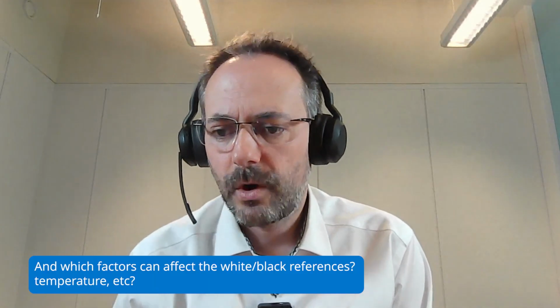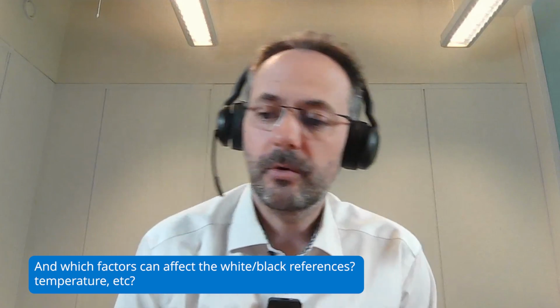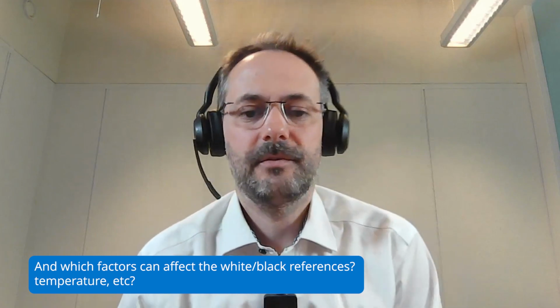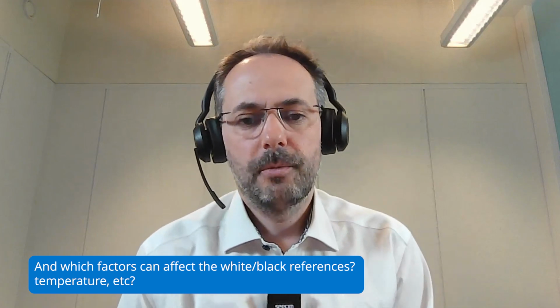Which factors can affect the white and black reference, temperature, etc.? Okay, I think I already gave a kind of answer, but I can repeat it. About the white reference, it sees mostly the illumination. So it is actually seeing the incoming light. So what can affect it? It is if you change any camera parameter, for example, the integration time.